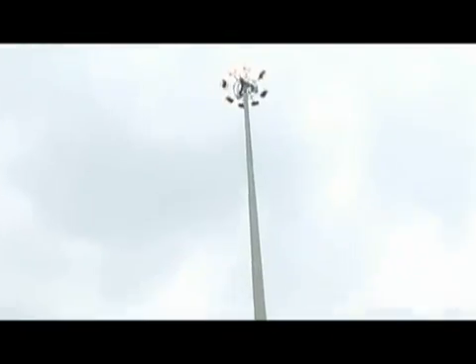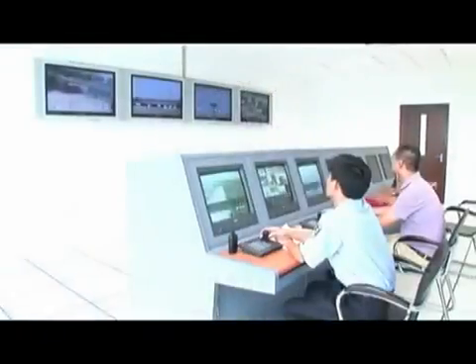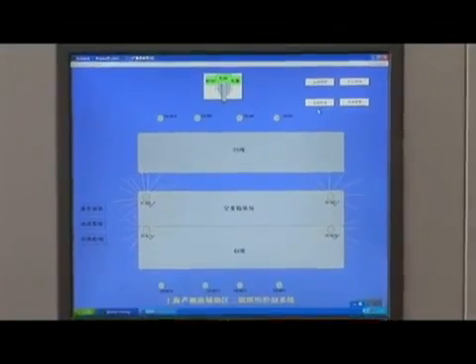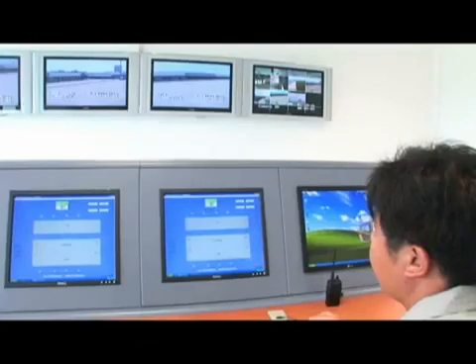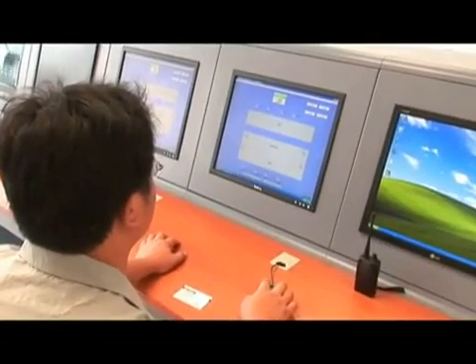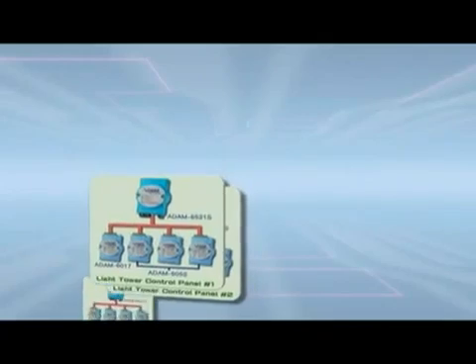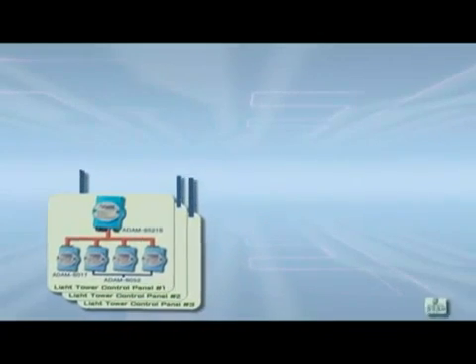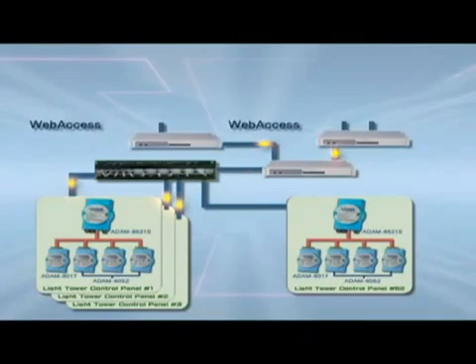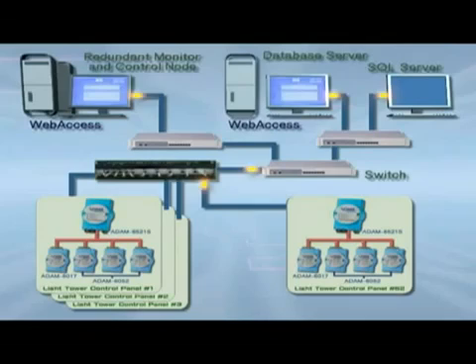In the Port Container Yard Lighting Control System, Advantech provides all the software, including on-site data acquisition, data transmission and supervision, and historical data management at the command center. The whole system is based on a browser-server structure, coupled with a double redundant network to ensure system stability. All the image design, system allocation, software management and database installation can be done remotely by the use of standard IE browsers.